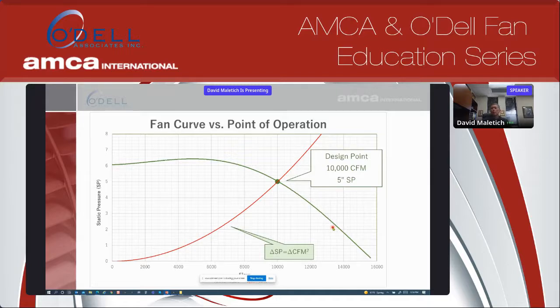Generally, when we have fan performances, it's always at the fan's inlet conditions. Actually, let me rephrase that. When we see temperature and other conditions, we always put that at the fan inlet. But when you see static pressure for fans, that is the static pressure at the inlet and outlet combined. So if you see 10 inches of pressure for the fan, that could be 5 inches of negative pressure at the inlet and 5 inches positive at the outlet. Or it could be -2 at the inlet and +8 at the outlet, or some variation that adds up to 10 inches of pressure. So it's kind of a combined measurement there. Does that answer your question, Pat?